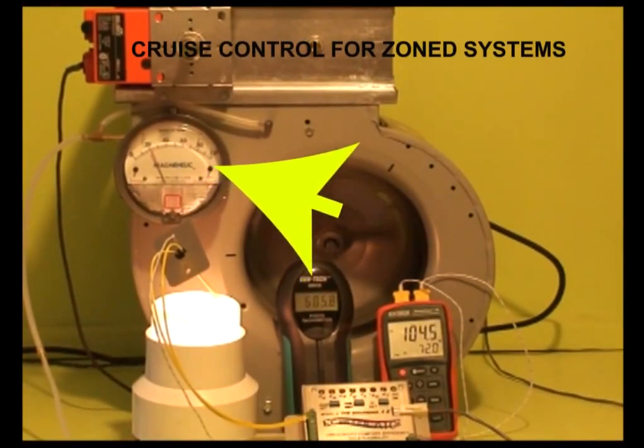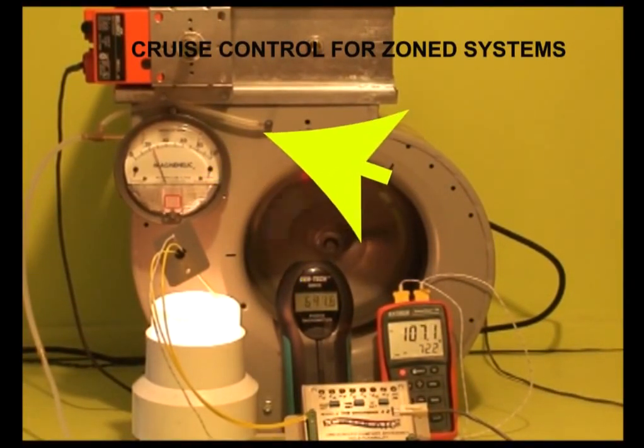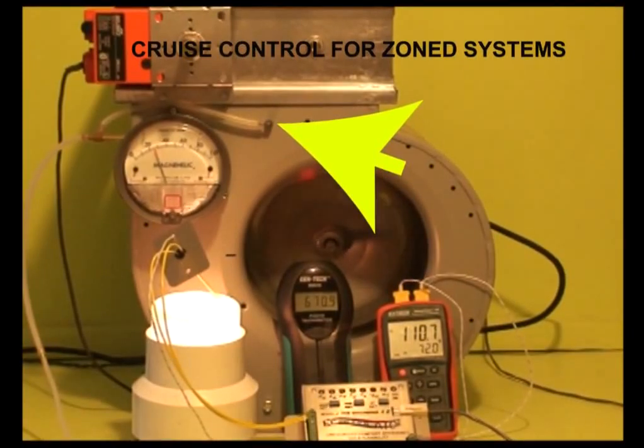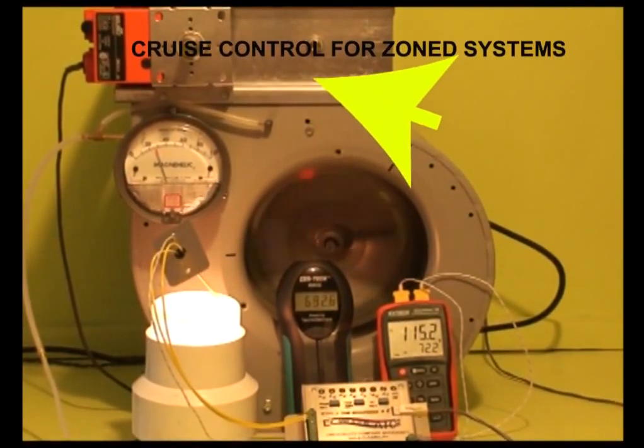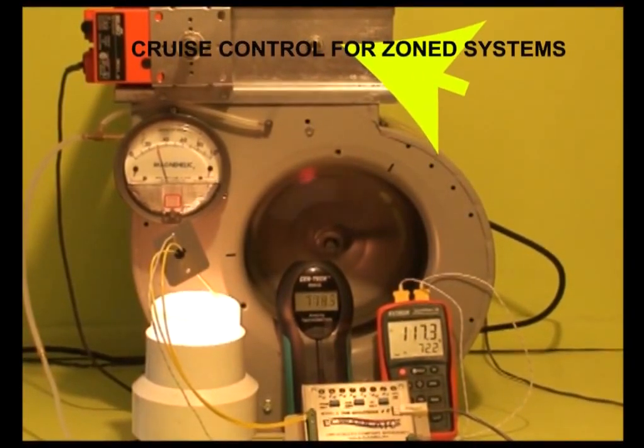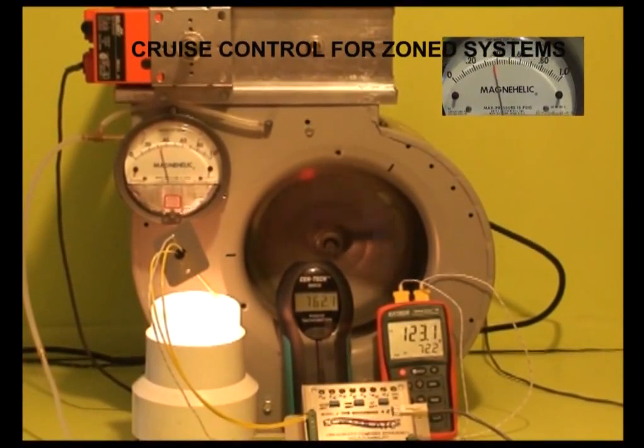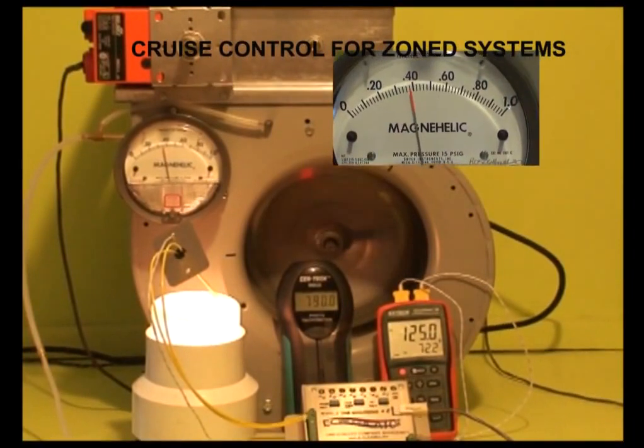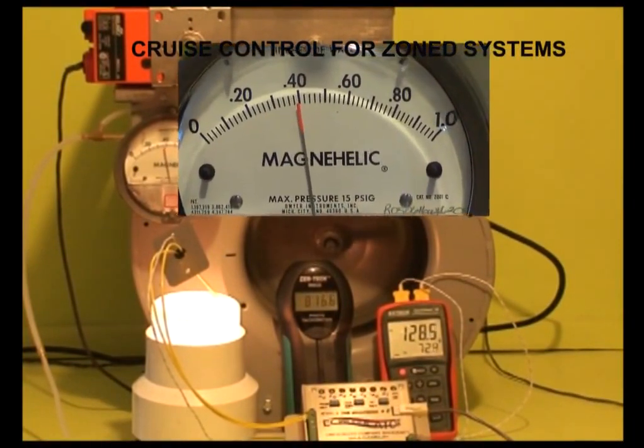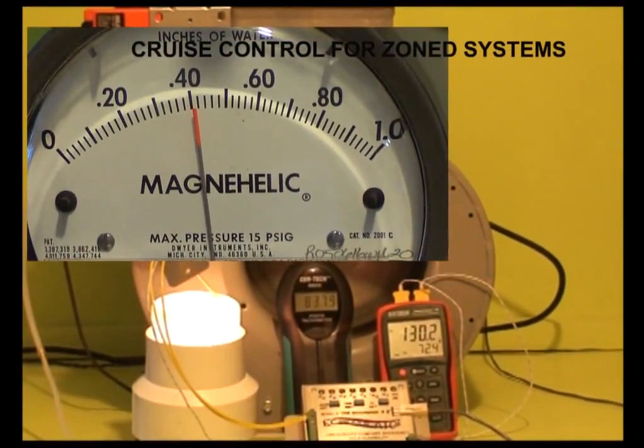This is a terrible place to sense pressure. We're using it to demonstrate the ECM modulator's capability. And this is a motorized damper, more on that in future videos. If the temperature at the sensor builds up, the blower speed increases and so does the duct pressure. The duct pressure settles out at about 0.4 inches water column.